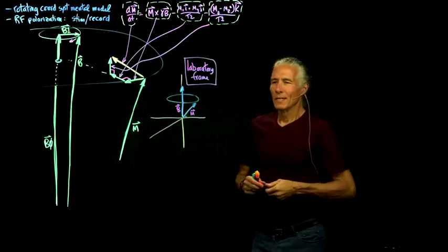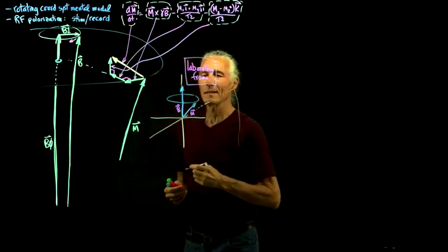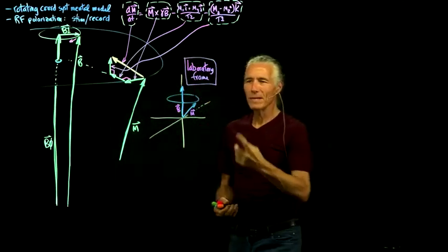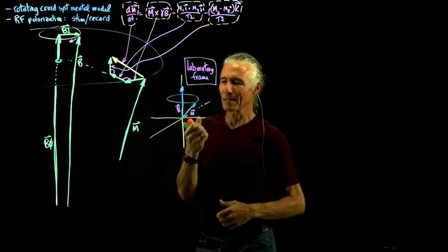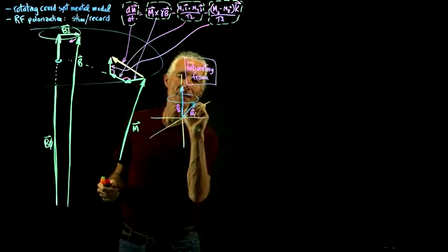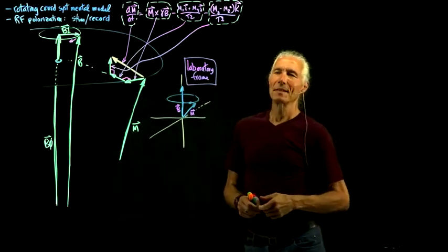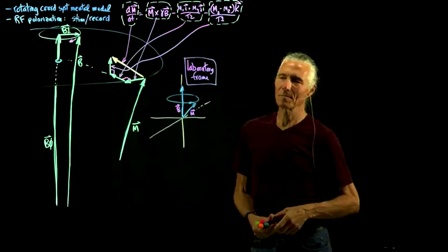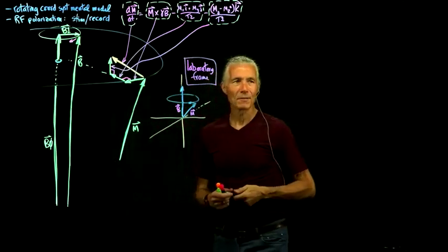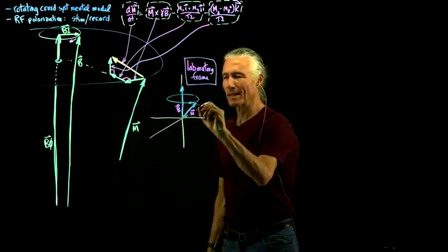So to move to the rotating frame, all we do is assume that we're spinning around at the same speed as the precession. So the precession's going around in this direction. For our magnet, at 2.89 Tesla, it's 123 megahertz, 123 million times a second. So if we spun ourselves around at that rate, what would happen? We would just stop this M vector in its tracks.